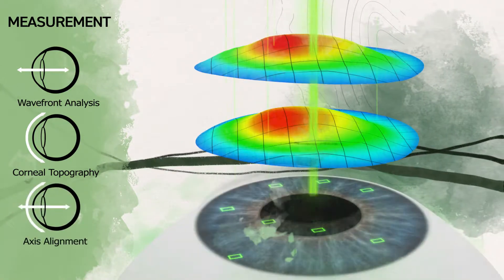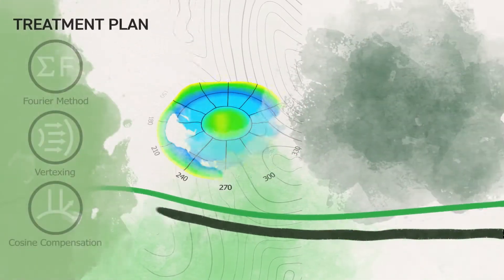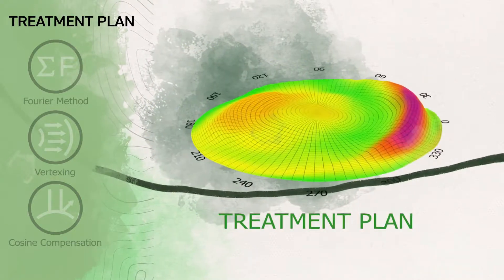By capturing an iris registration image, the system is able to precisely align the two measurements on the eye. Both of these measurements—the wavefront analysis inside and corneal topography outside—will be fully integrated into the treatment plan.